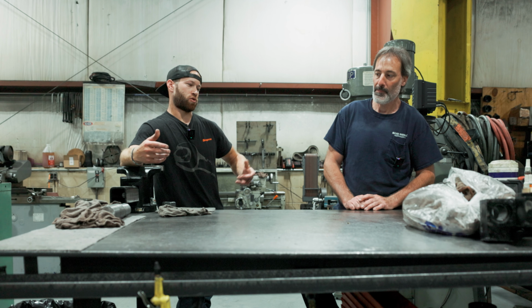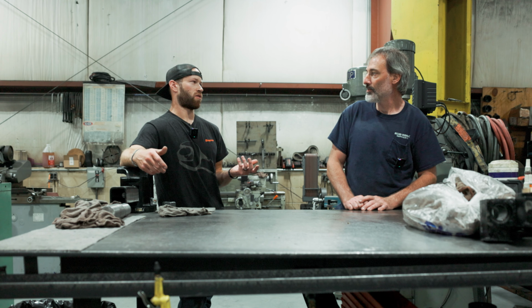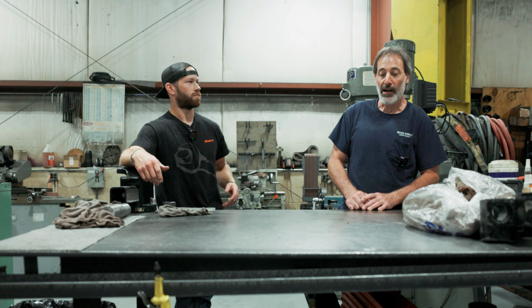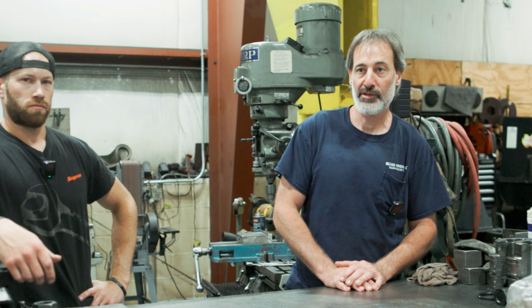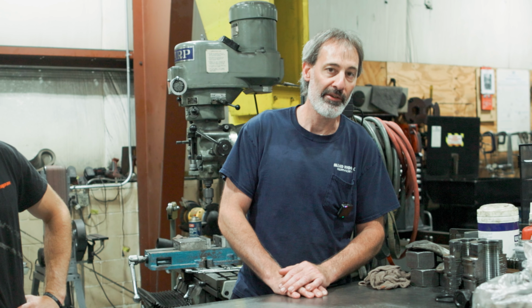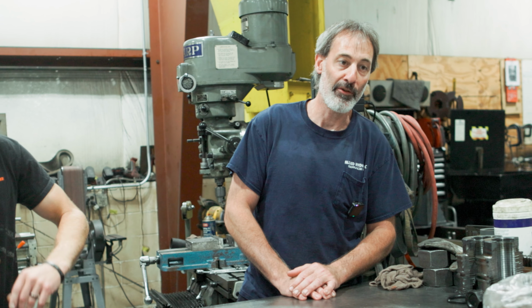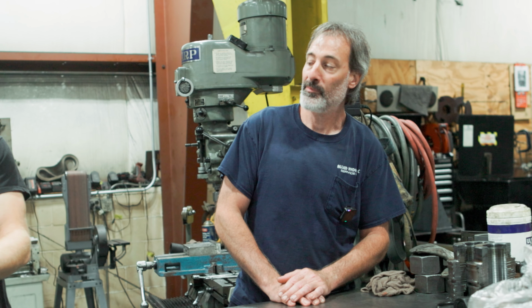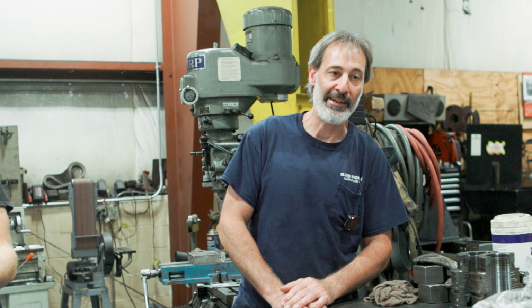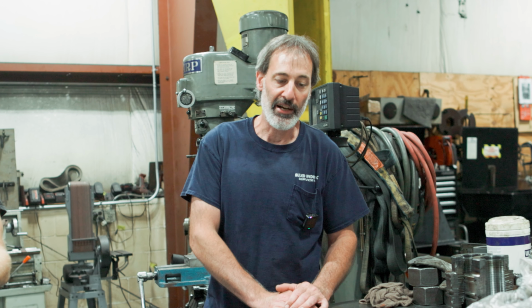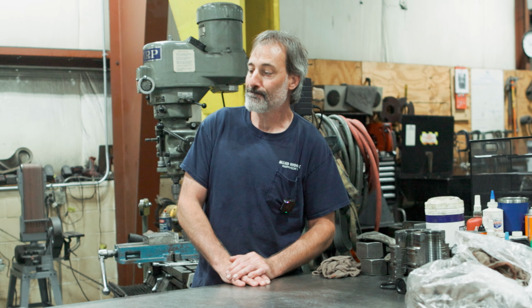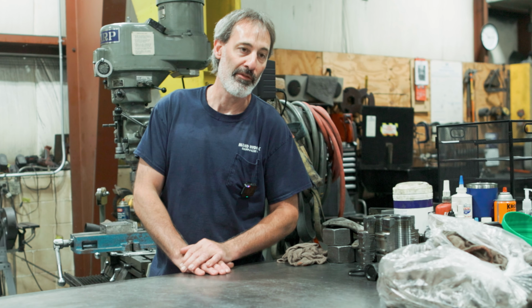So Tim, I have a machine, what's some common causes I have for overheating or just failure of my system? One thing that we didn't cover is normal wear and tear, just high hours on a machine. When you have high hours, bearings tend to fail, and that is going to be some of the worst contamination. If bearings fail, you get little tiny fragments of metal floating in the system.